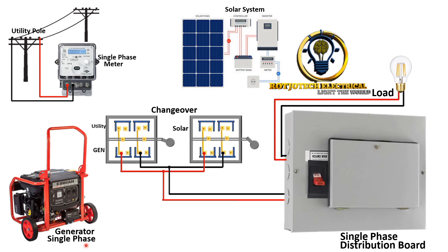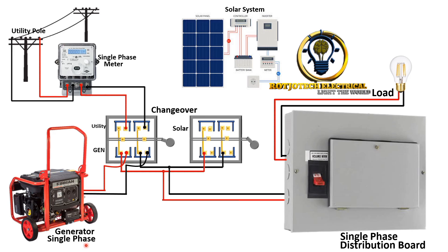Now that the load side is done, let's connect the power sources. We connect the live and neutral of the utility to the first input of the first changeover switch. Then we connect the generator to the second input of that same changeover switch. The output of this changeover switch is the load, which we have already done. Then we come to the second changeover switch and connect our solar system — live and neutral — to it. Very simple and straightforward.